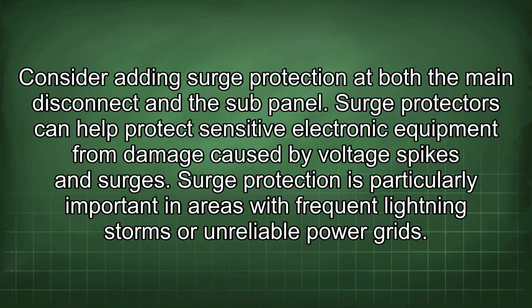Consider adding surge protection at both the main disconnect and the sub-panel. Surge protectors can help protect sensitive electronic equipment from damage caused by voltage spikes and surges. Surge protection is particularly important in areas with frequent lightning storms or unreliable power grids.